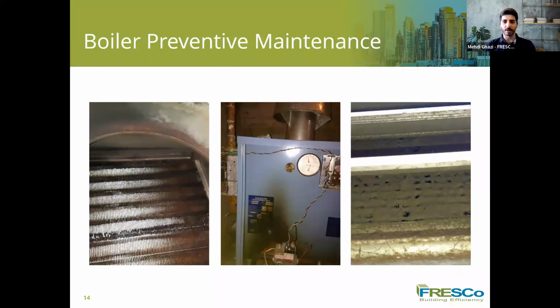In the right photo, you can see a clogged combustion air intake. Sometimes the air intakes are very close to our laundry room, so we need to make sure that the lint from the laundry room won't clog the air intake. That can happen also with grass clippings or leaves or even birds' feathers, which I had the same experience with when I was working for a commercial building in downtown, because in downtown we have a lot of birds, and that could be an issue that needs to be checked quite regularly. This issue could result in a lazy flame, not a good quality flame, and we will just have some gases going up the flue vent without using the heat which is in the gas.